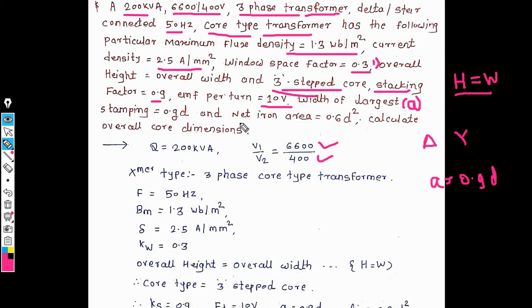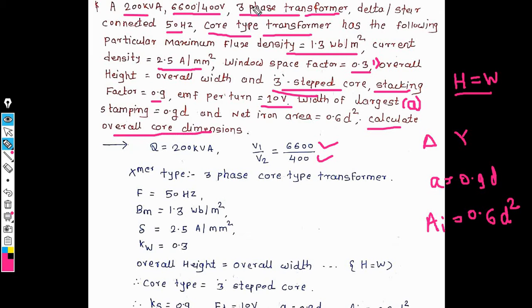The width of the largest stamping, a, is equal to 0.9d. The net iron area Ai is given as Ai = 0.6d². We need to calculate the overall dimensions of this three-phase core-type transformer, following the same procedure as for a single-phase transformer but using the appropriate output equations and net iron area formula.